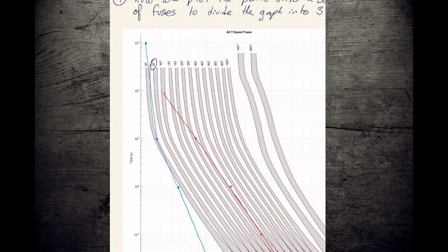And now our customers are in the dark. Why are they in the dark? Nothing broke. There was no fault. You're going to get there as the lineman on call, and you're going to patrol the line, and you're going to say, I don't see anything wrong. I wonder what happened. And now you're in the awkward spot of, do you keep searching, or do you put another fuse in and just hope that the problem has gone away? So the 6T fuse, a little bit too small.